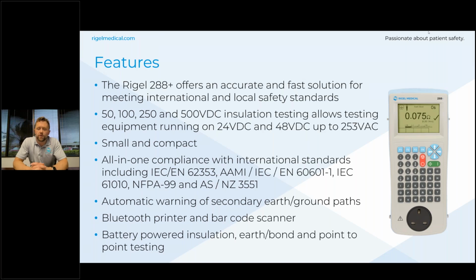It also has automatic warning of secondary ground paths. So if your medical device is connected to anything that allows leakage currents to flow back to ground and not through the analyzer, then the 288 will notify you of that to make sure you're getting accurate leakage results. There's also some ancillary devices that we provide with the 288, specifically a Bluetooth printer for printing out results or labels, and a barcode scanner for inputting your asset management details.